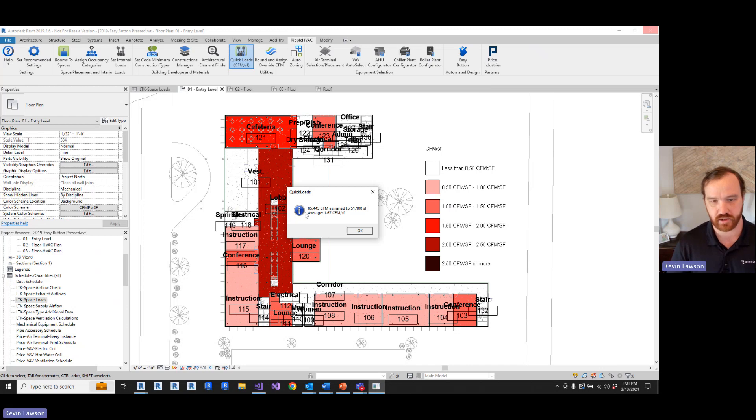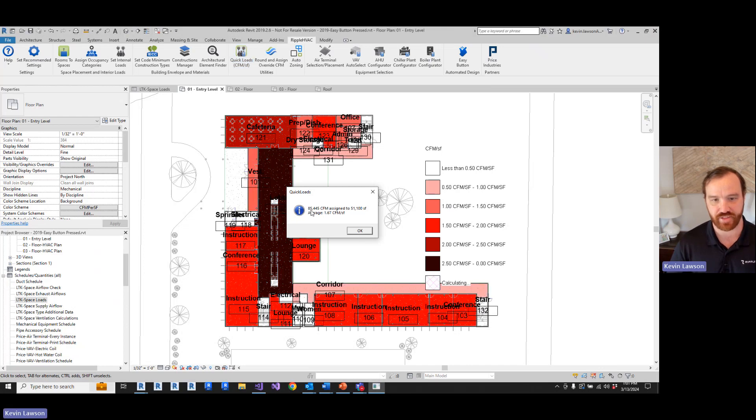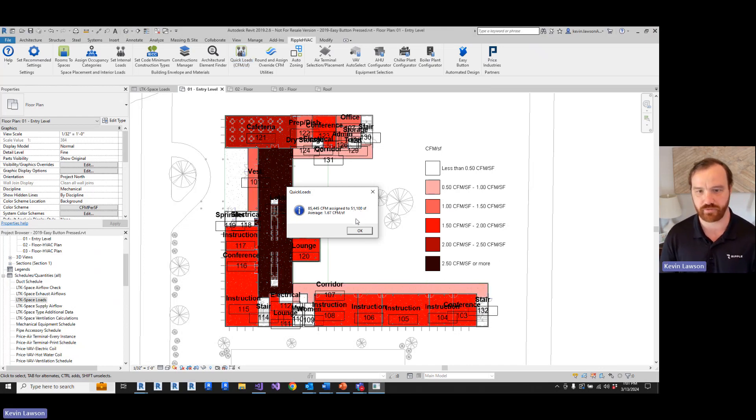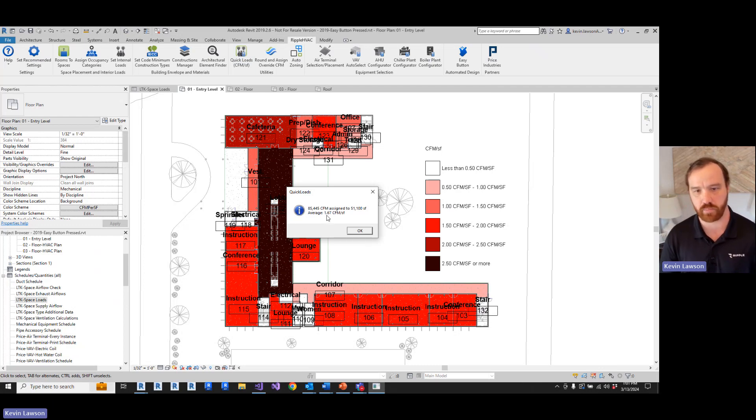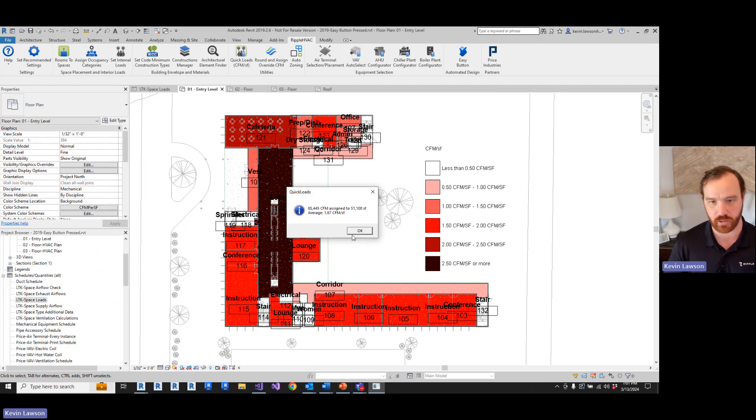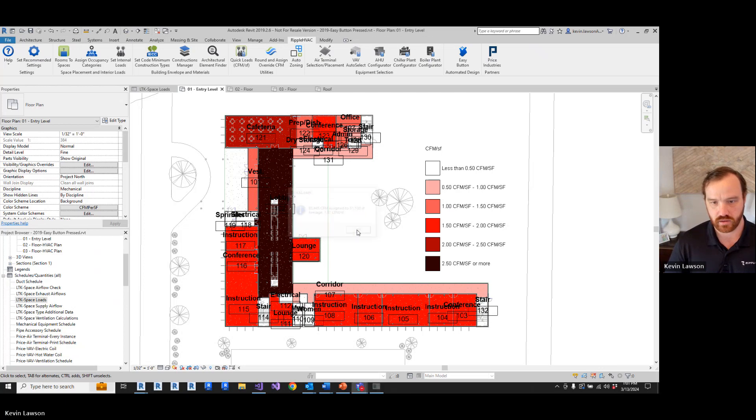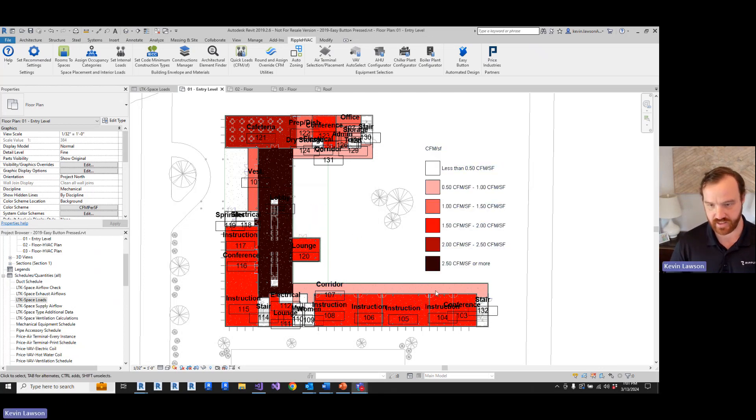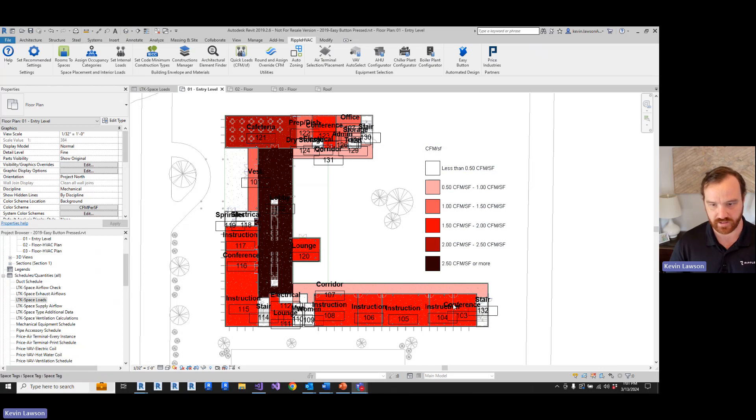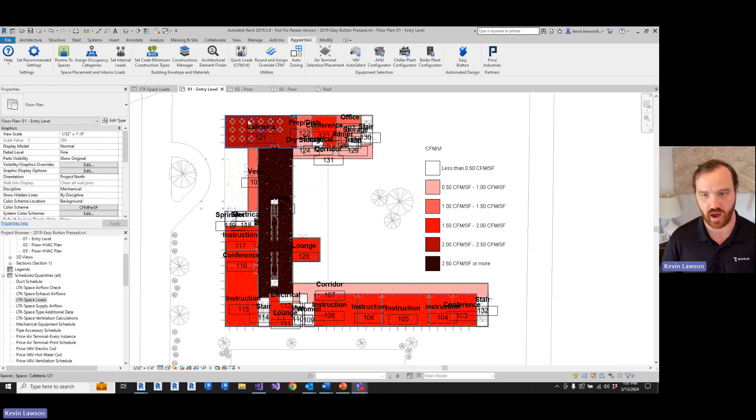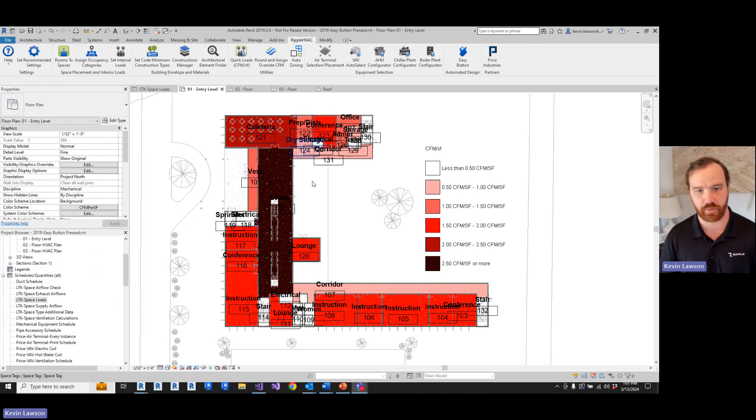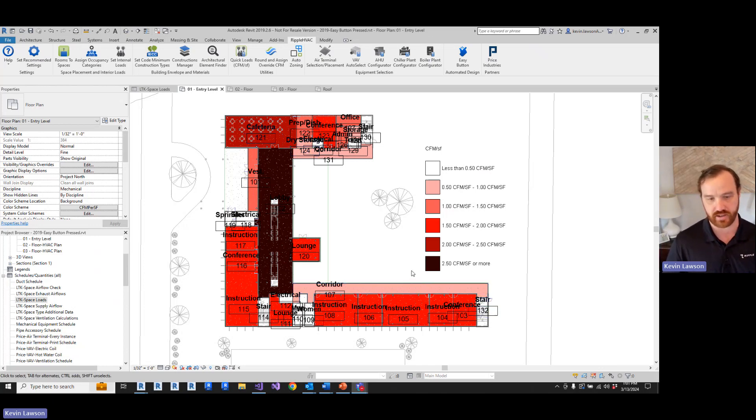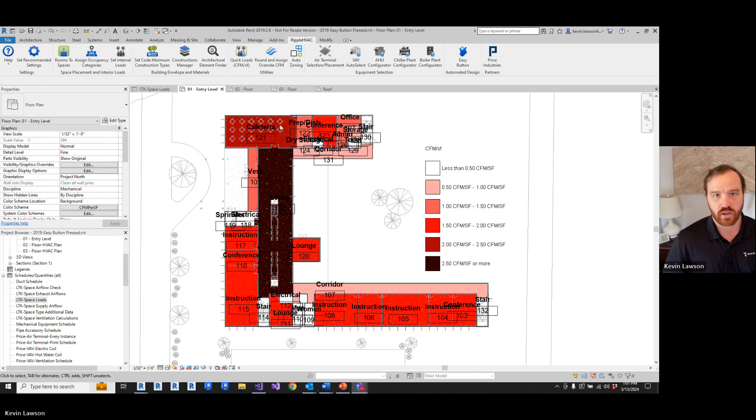And then we'll just run quick loads again. So now you can see it applied 85,000 CFM to 51,000 square feet, more at 1.67 CFM per square foot. So as the occupancy density gets higher, you get a higher airflow per square foot, but it's just overall higher because it's in a different climate zone.